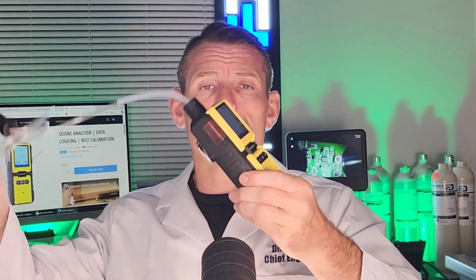So what that means is that it's drawing the air onto the sensor. It's a forced system, folks. It's aspirated, so it has a pump. And that's actually an advantage because you can undertake very fast response measurements in an indoor situation. And at the same time, you can connect various probes. It comes as standard with a 4-foot telescopic probe. And at the end of the probe, we connect the tubing to the barb with our 1/8 inch standard silicone tubing, folks. So the setup is something like that.